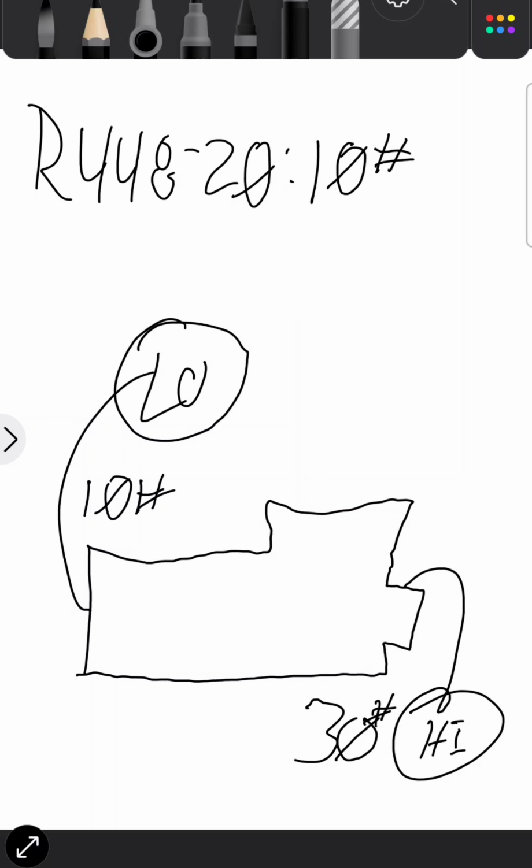And then according to that Emerson bulletin, I shouldn't really start being concerned until this number gets down to 20, right? Because it said it can maintain good oil down to 10-pound net. But typically, once I see it start dipping below that 20-pound mark, I start getting concerned and I start looking into what the issue is. Okay, so that's how you get your net oil pressure.